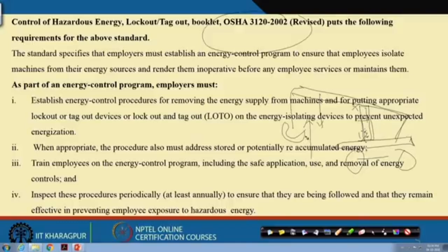So, stored energy means, he says, the stored energy also should be made zero, and you put a mechanical stop here before people work. With the stored energy, people cannot work. We have mechanical stored energy, electrical stored energy, hydraulic stored energy; we will talk about those things. So, OSHA says that also should be made zero, and you have to train the people and inspect periodically whether these things are in position or not. This is the requirement of OSHA.